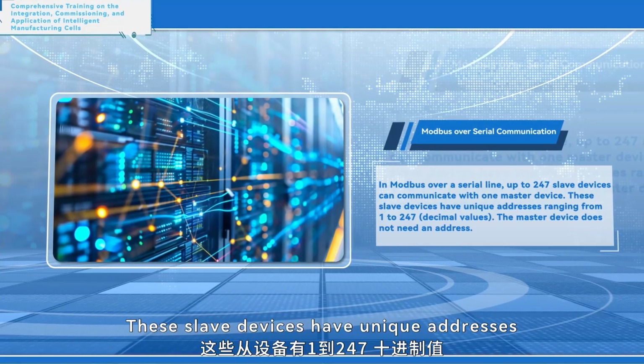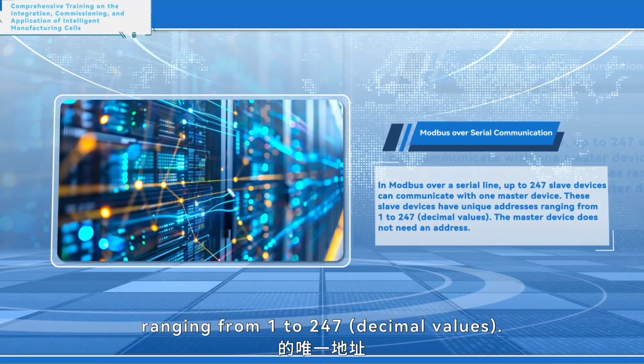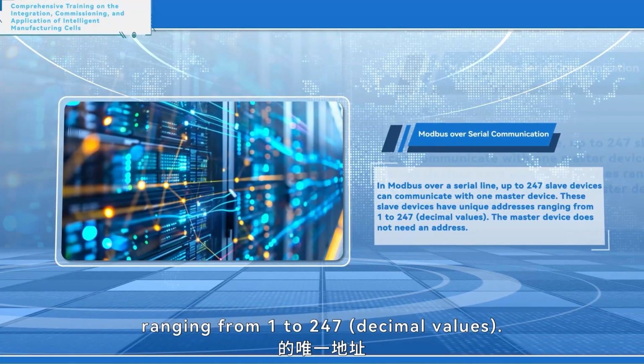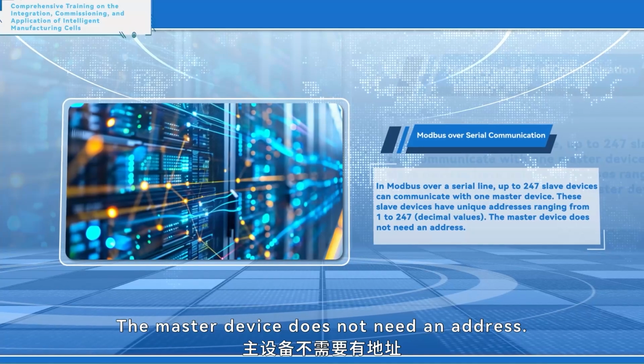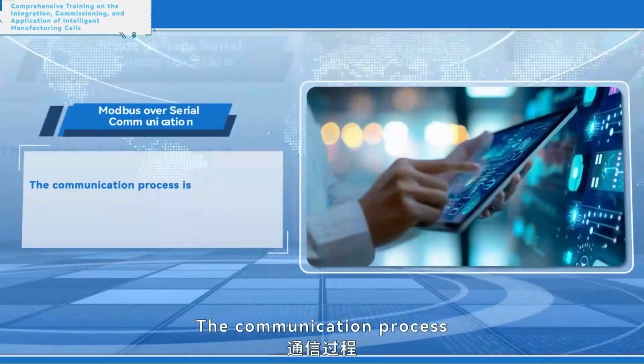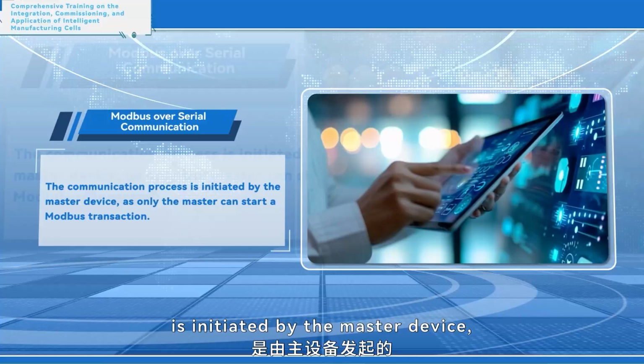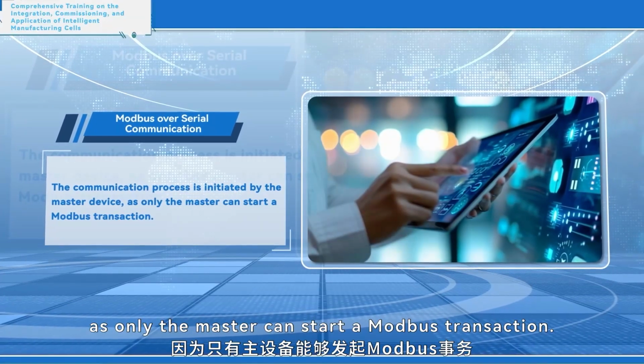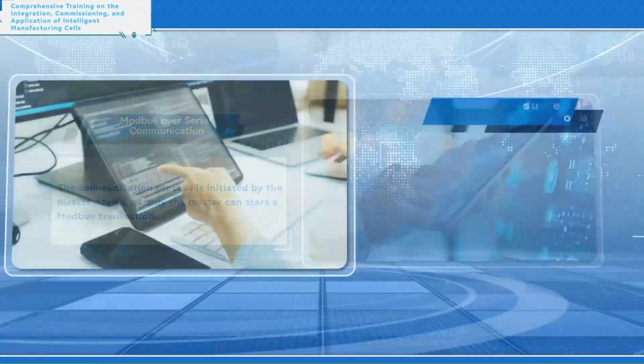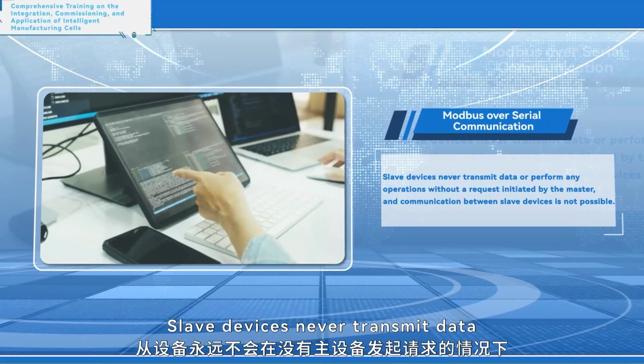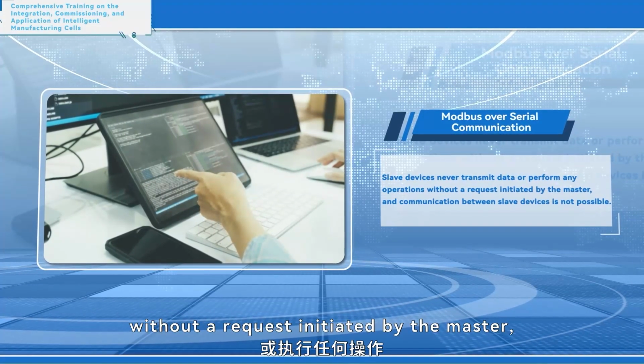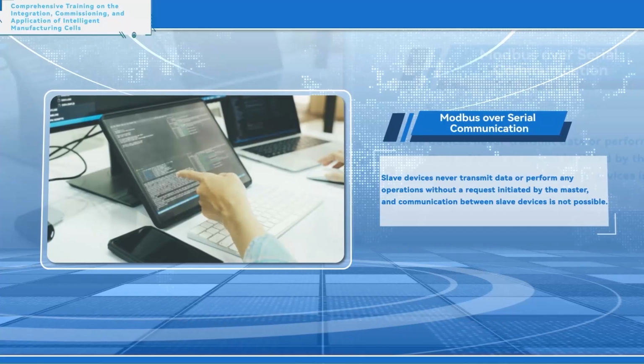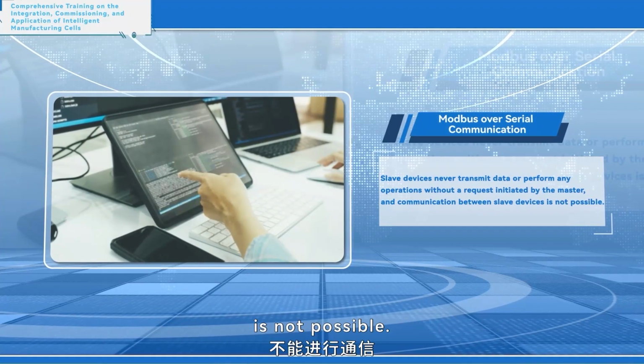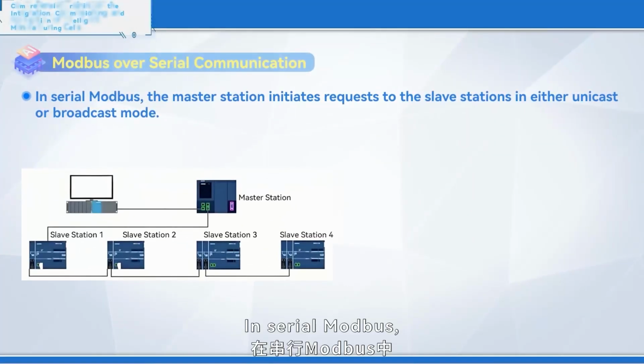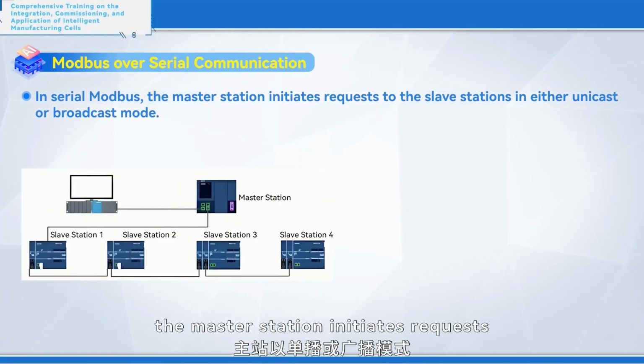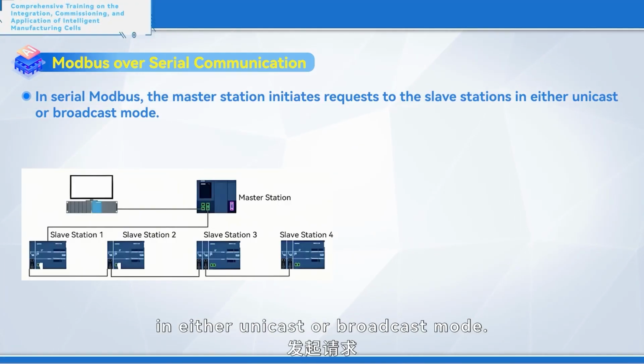These slave devices have unique addresses ranging from 1 to 247 decimal values. The master device does not need an address. The communication process is initiated by the master device, as only the master can start a Modbus transaction. Slave devices never transmit data or perform any operations without a request initiated by the master, and communication between slave devices is not possible.